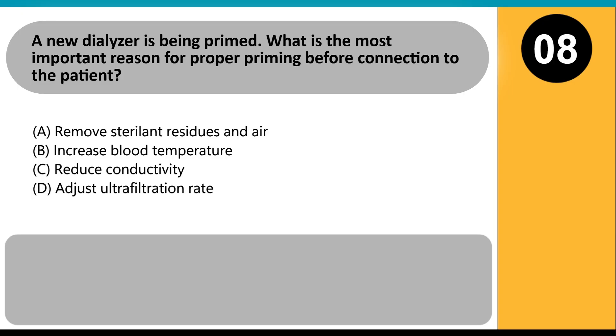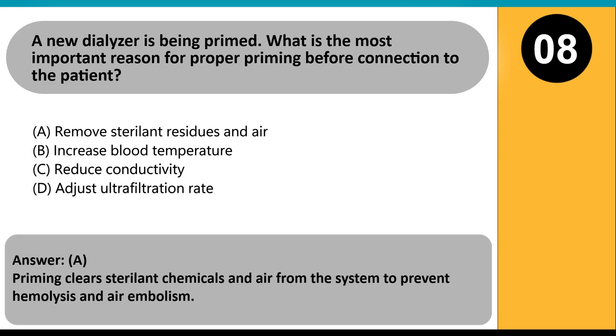A new dialyzer is being primed. What is the most important reason for proper priming before connection to the patient? A. Remove sterilant residues and air. B. Increase blood temperature. C. Reduce conductivity. D. Adjust ultrafiltration rate. Answer A. Priming clears sterilant chemicals and air from the system to prevent hemolysis and air embolism.